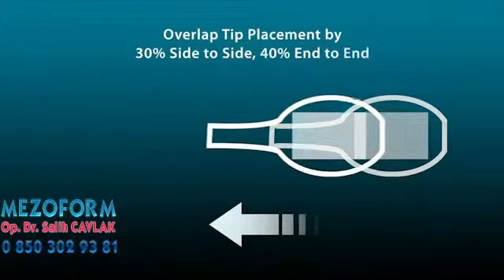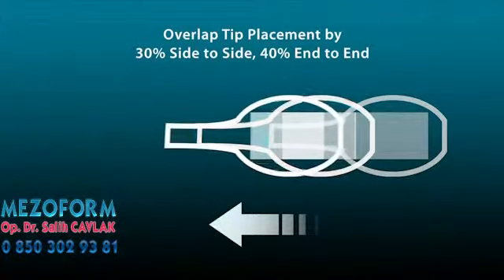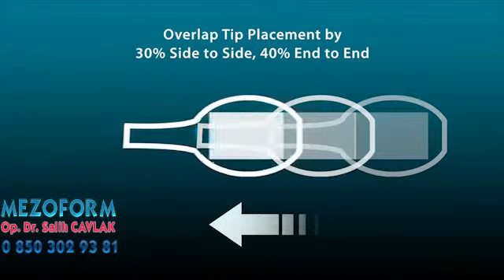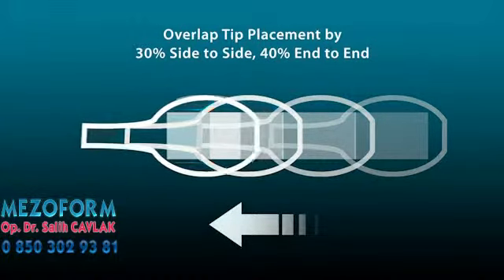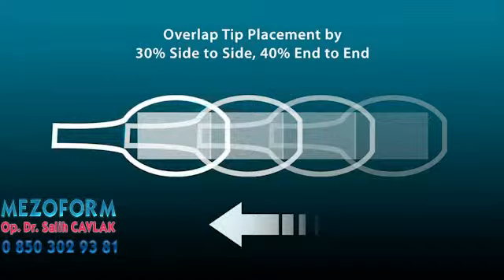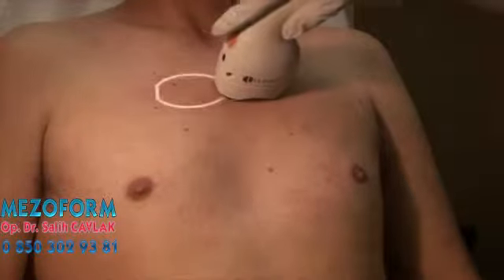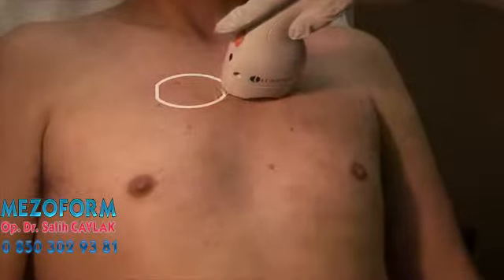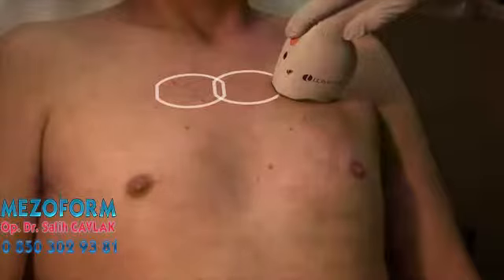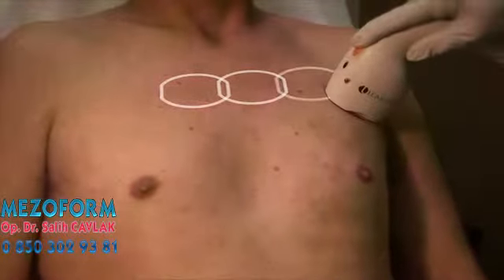The treatment area of the handpiece is 22 by 35 millimeters squared, which is smaller than the footprint of the handpiece. Therefore, to assure complete coverage, it is necessary to overlap approximately 30% side to side and 40% end to end. The pick-and-place technique should be used moving from area to area, providing total coverage by overlapping the treatment area.